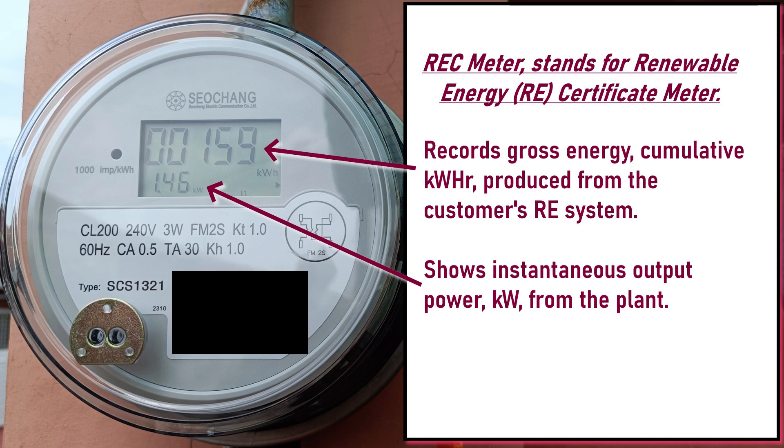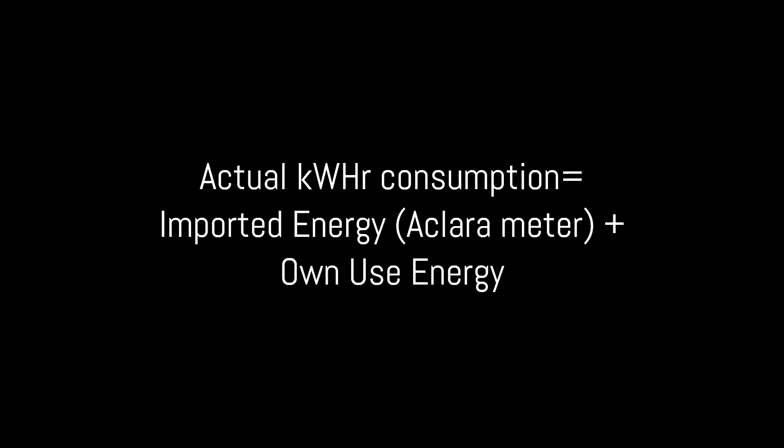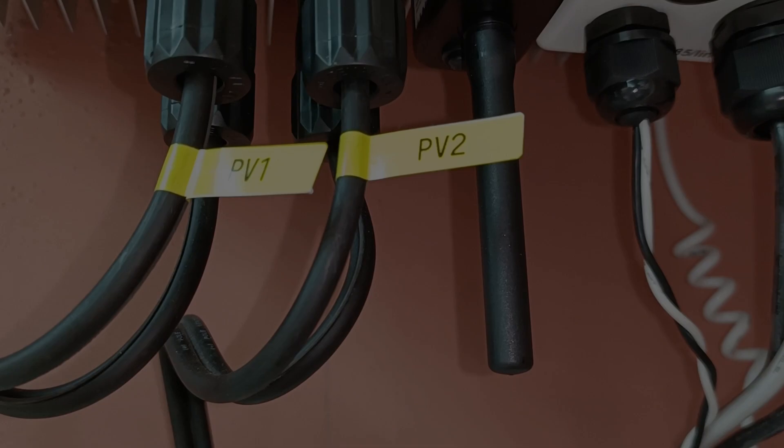The REC meter here also shows the real-time kW power output of the solar power plant. The relationship between the bi-directional meter and the REC meter is this: both meters are used to compute for the actual kWh consumption in the electric bill. Actual kWh consumption is imported energy plus own-use energy. Own-use energy is the energy registered by the REC meter minus the exported energy, so you need the readings of both meters in the utility electric bill.